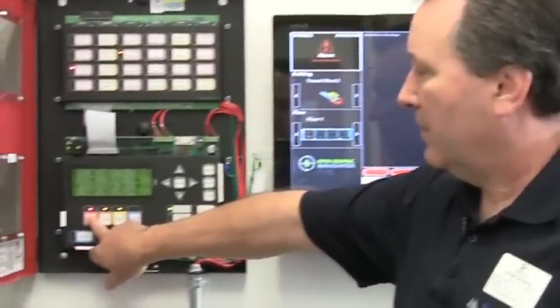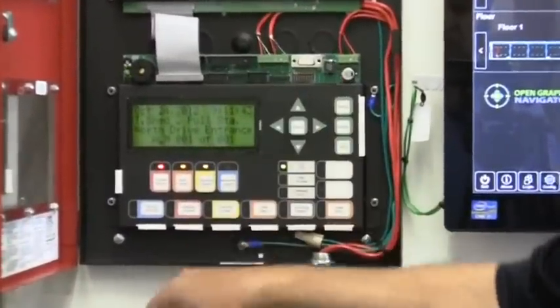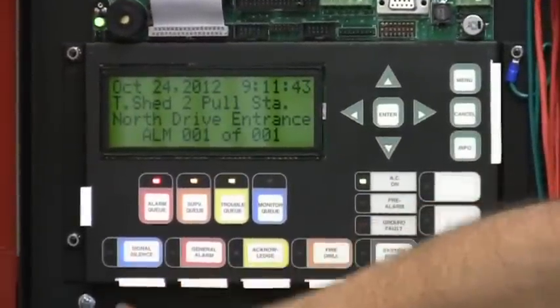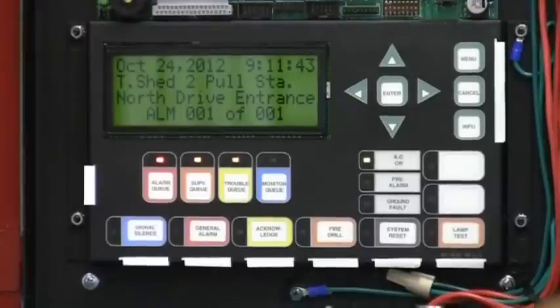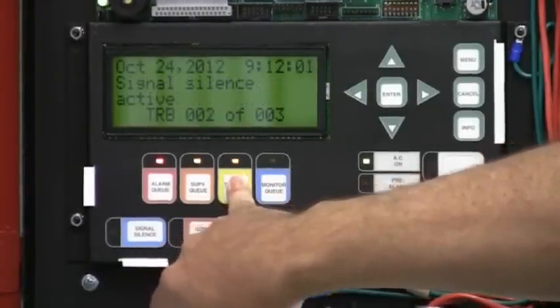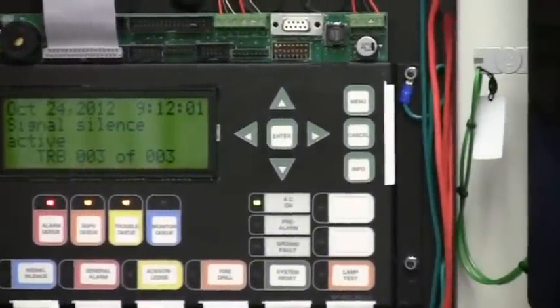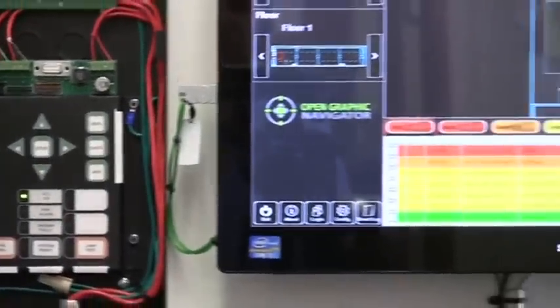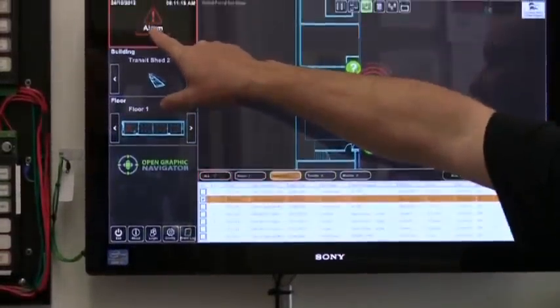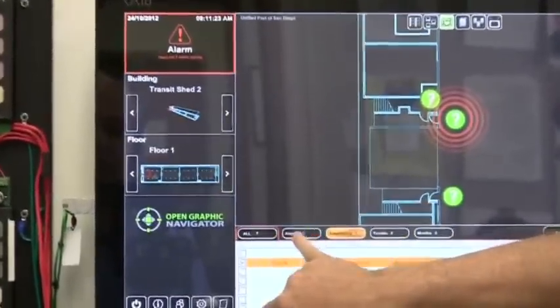Pushing the flashing light allows us to establish a silence on the panel itself. We're going to go ahead and stop the alarm signals. When we do so, we get the signal silence event trouble. So now in the system we have multiple events, and the way that multiple events would be identified — the first priority is the alarm condition in the system.